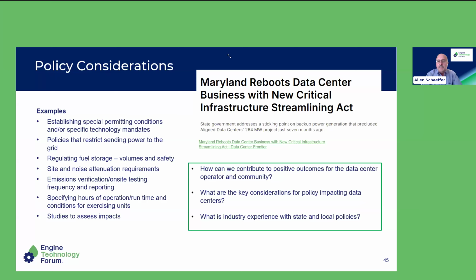That immediately created concerns in terms of the data center's ability to meet their objectives in terms of being able to sustain power for an extended period of time before needing fuel replenishment. I think the initial volume storage allowed was like 1,500 gallons, and that was probably pretty unworkable for most kind of settings. That 1,500 gallons could be consumed rather quickly in a situation where that generator was running under full load for a continuous amount of time.